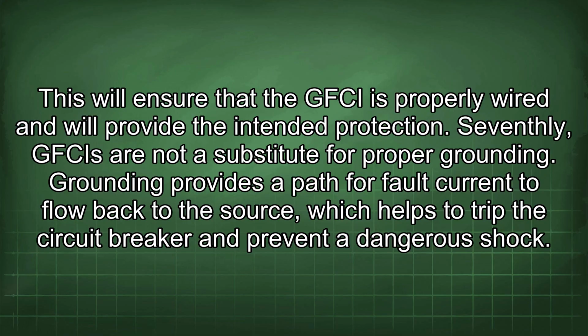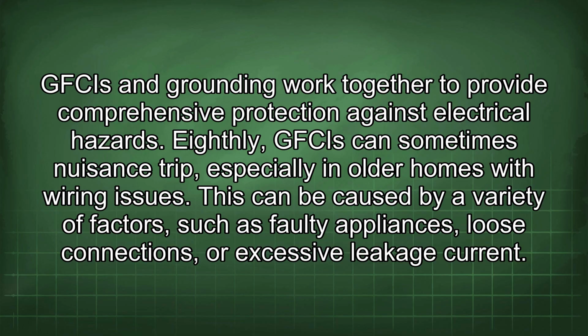Seventhly, GFCIs are not a substitute for proper grounding. Grounding provides a path for fault current to flow back to the source, which helps to trip the circuit breaker and prevent a dangerous shock. GFCIs and grounding work together to provide comprehensive protection against electrical hazards.